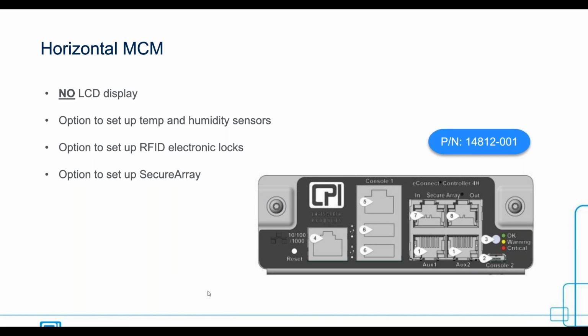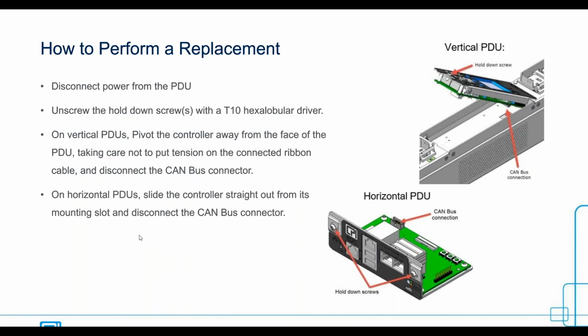Notice how the horizontal is more compact in its layout, and the features are set very differently compared to the vertical controller module. To access the horizontal controller module settings, you will need to use CLI or the web GUI to make any changes. Now let's review how to perform a replacement of a field replaceable main controller module. The first step is to make sure to disconnect power from the PDU to avoid the risk of electrostatic discharge that could damage the MCM. This is a very essential step.